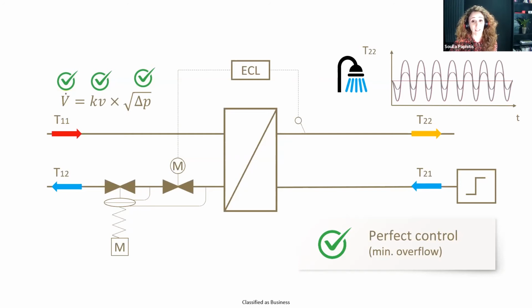Since the system is dynamic and the differential pressure is changing all of the time, this will in most cases give you a very poor control. And you can see that by the changing temperature in the graph at the top where the domestic hot water is coming from. With upgrading the substation with a differential pressure controller, we can achieve full authority over the flow control. And in most cases, we can achieve a perfect control.